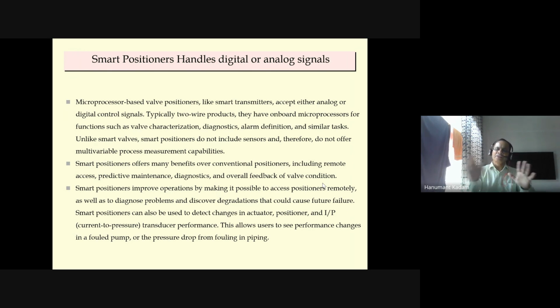So you can access the positioner through Modbus, as well as diagnose problems, and discover the degradations that could cause future failure. So you can know in advance. Smart positioners can also be used to detect changes in actuator, positioner, and I2P performance, and this allows the user to see the performance changes in a faulty pump or the pressure drop across the fouling of the pipelines.